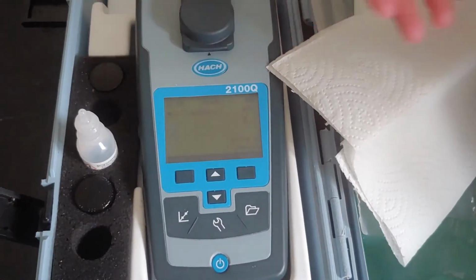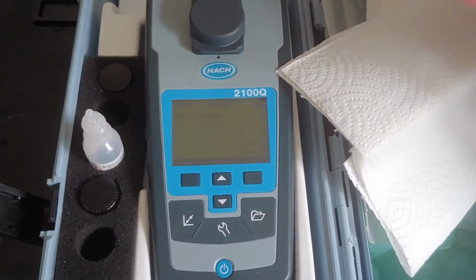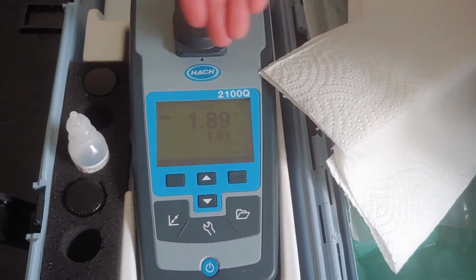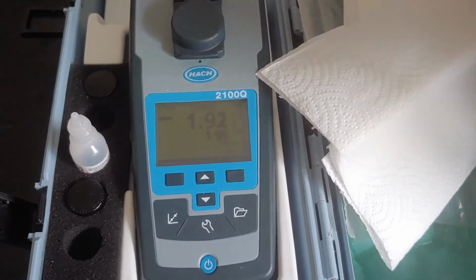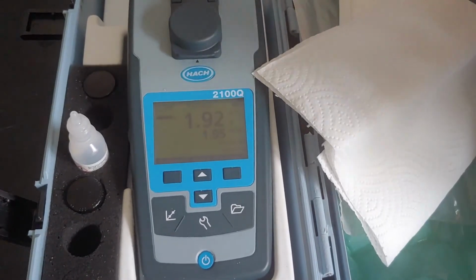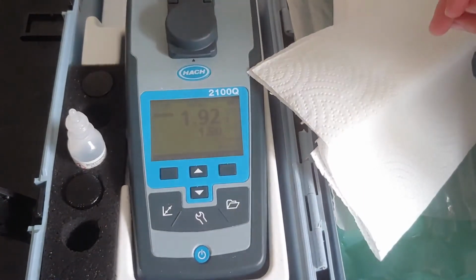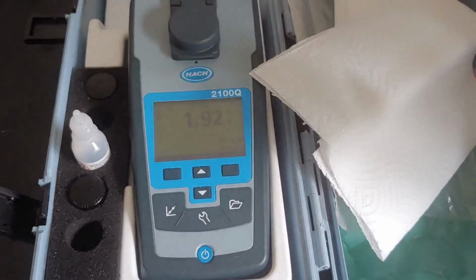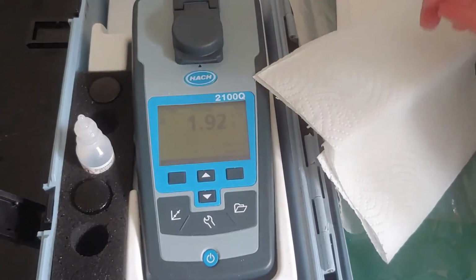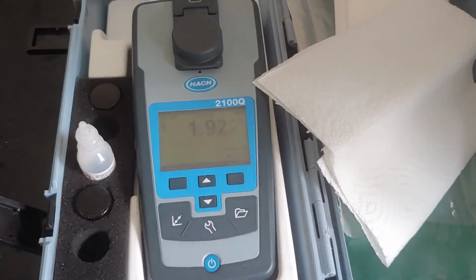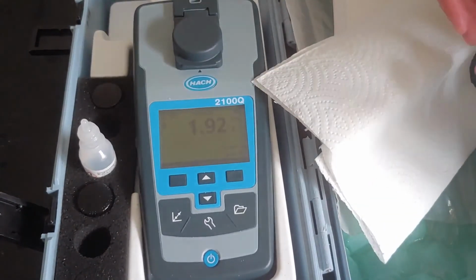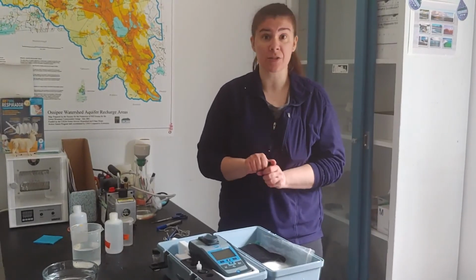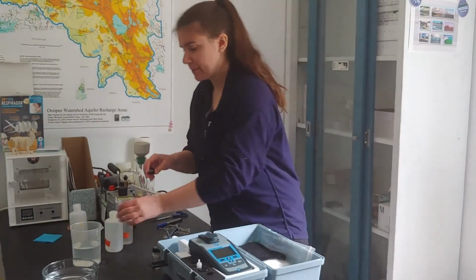And again, much like with the meters that we use for conductivity and dissolved oxygen, I have this stabilizing bar going across. Now you will see numbers tick through as it's trying to zero in on the correct turbidity number. From here, I will record this number on my data sheet and then proceed to do the second sample. Okay. Once I have ensured that my two turbidity readings are within the maximum allowable difference of 0.2, I am now going to just discard this water back into the river.